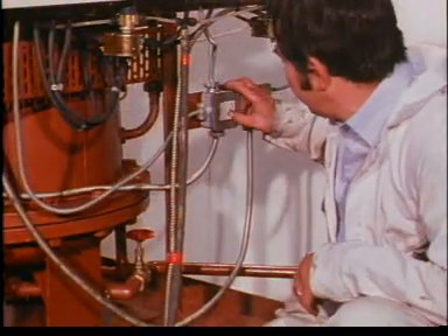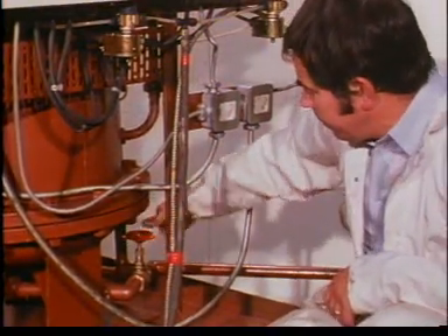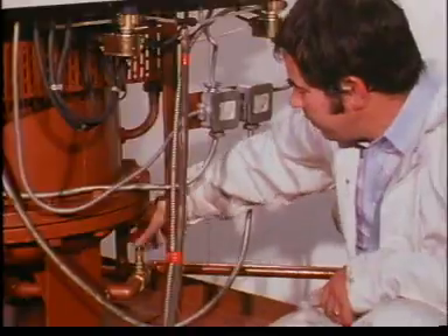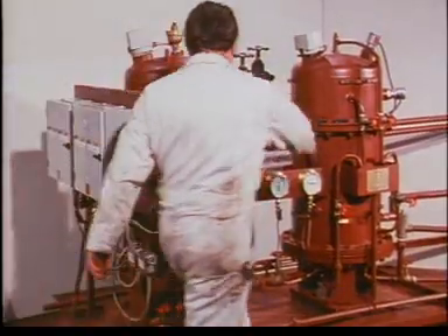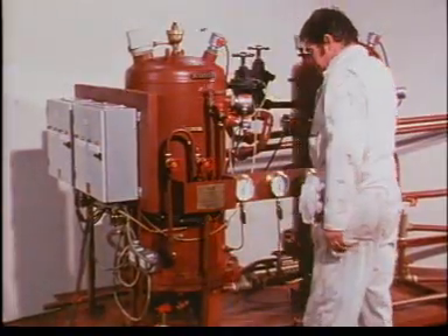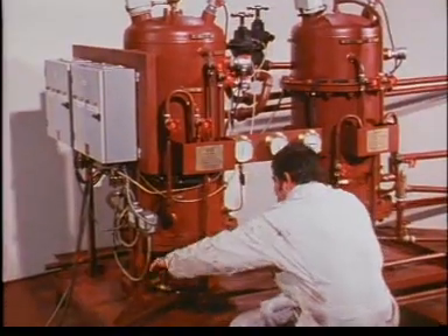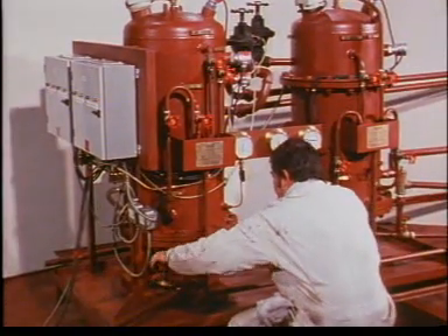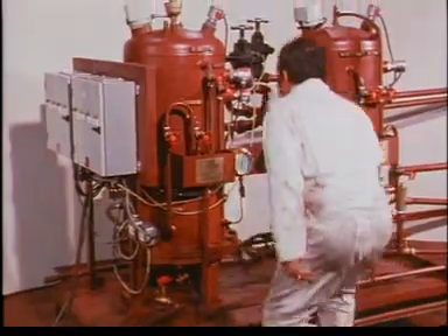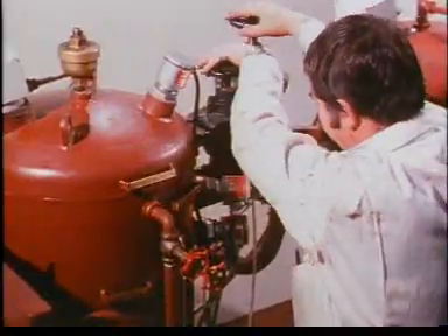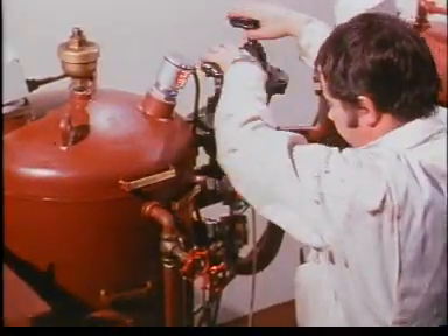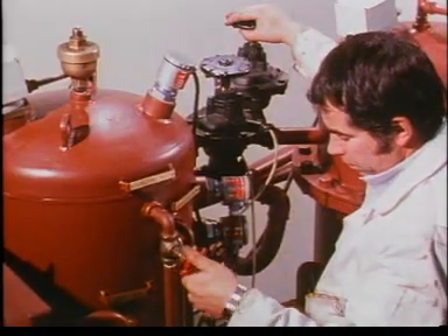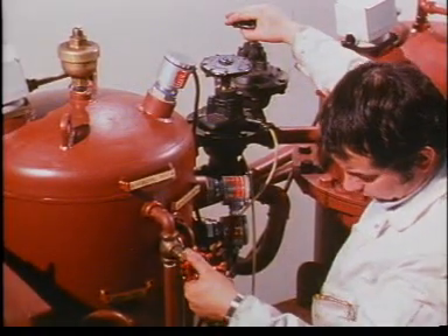When the system is full of clean water, switch on the electric heaters. The filling valve is now closed and the contents of the whole system are allowed to become hot. When the system is hot, clean water is pumped through it by once more opening the initial filling valve. Occasionally, the manual oil outlet valves are opened on both stage 1 and stage 2 to drain any oil.